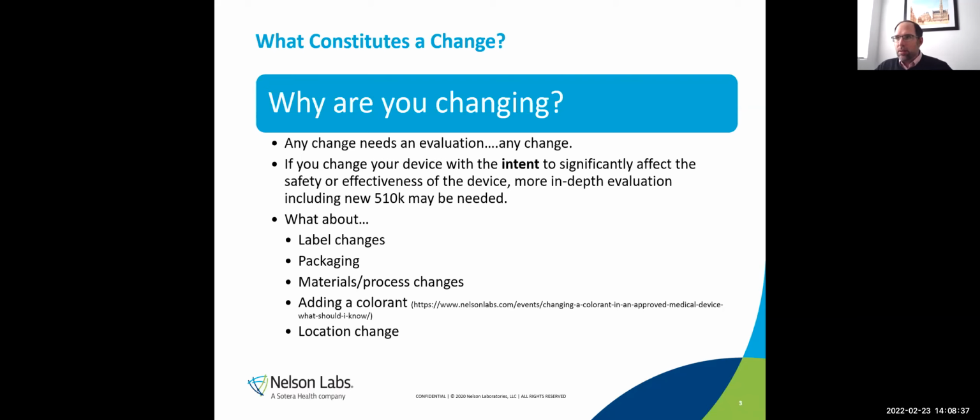When we see failures in biocompatibility, most of the time it has to do with process residuals and not the materials themselves. The other thing that I see a lot of people do is either change or add colorants to an already approved device. This was a little while ago, this was actually a very big topic, so much so that the FDA did its own webinar on it. If you want more information, I did a whole webinar and also a white paper on it.